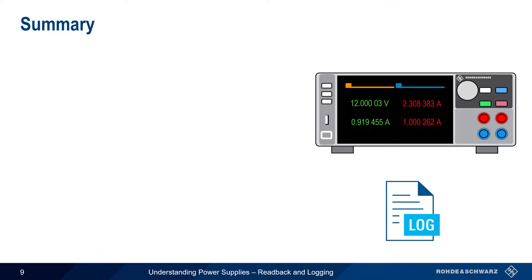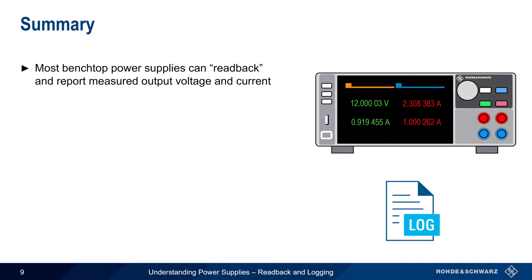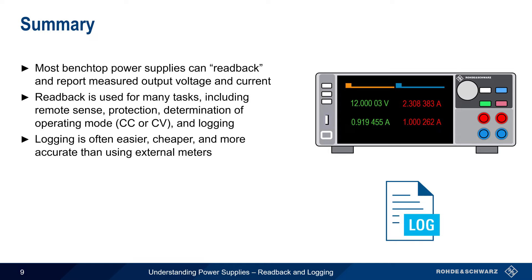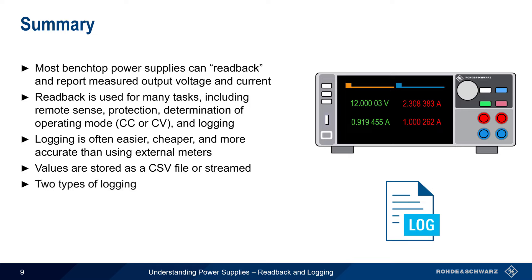Let's end with a brief summary. Most benchtop power supplies have a readback function that measures and displays the supply's output voltage and current. These readback values are used for many tasks, including remote sense, various protection functions, and determining whether the supply is operating in constant voltage or constant current mode. In this presentation, we focused on logging this readback data. Power supply data logging is often easier and cheaper than using external meters, and it also allows for greater accuracy, particularly when measuring two or more channels simultaneously. Log data is usually stored as plain text comma-separated value files, but in some cases it can be streamed to another device. There are two general categories of logging: standard logging is often limited to rates of about 10 samples per second, but some power supplies support a high-speed or fast logging feature with rates up to a half-million samples per second.